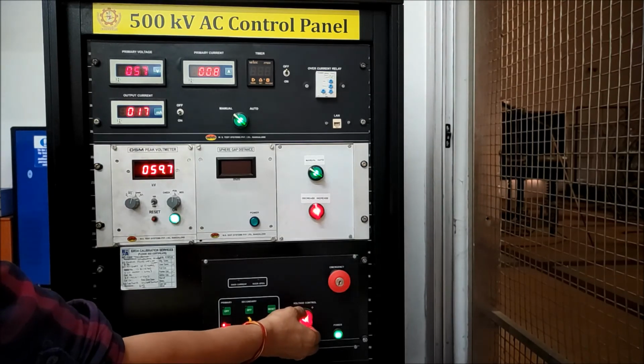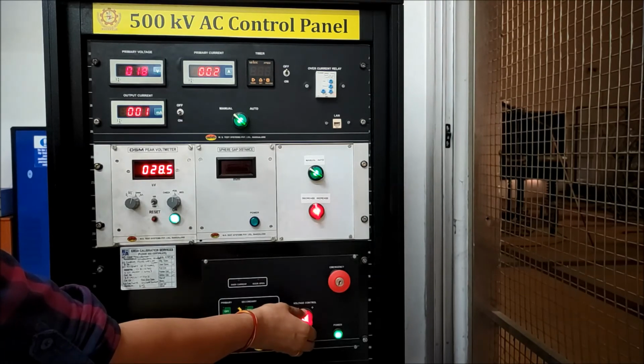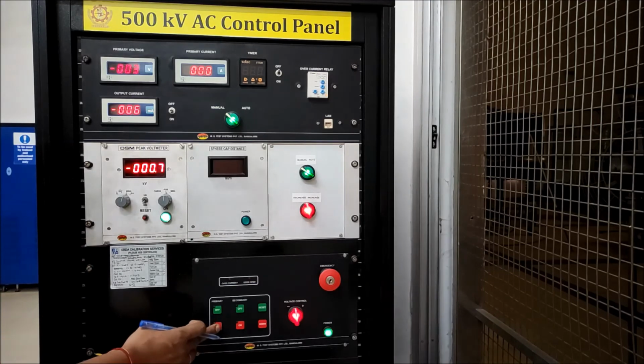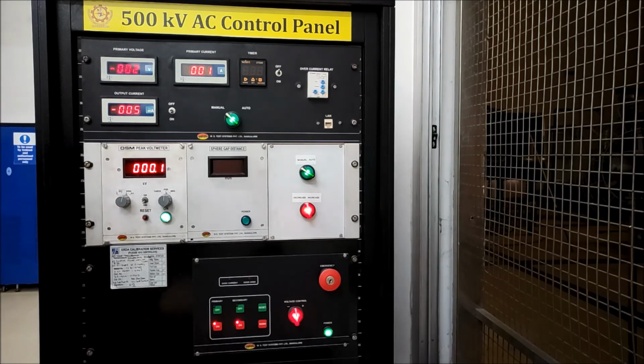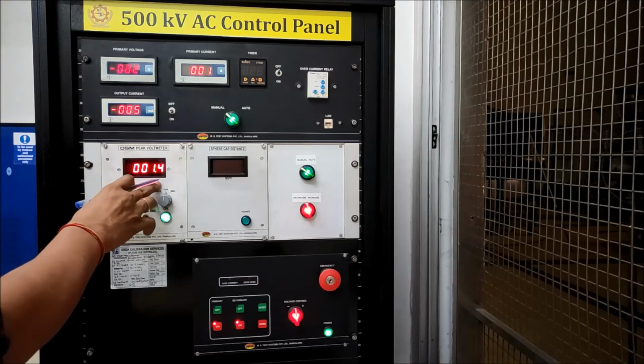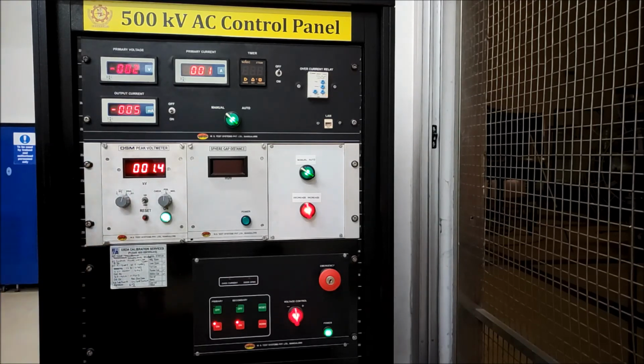Then the sphere gap distance is increased to 1.2 cm. Then again start your experiment. Now change the sphere gap distance to 1.2 cm, then start our experiment. Follow the same process: first switch on the primary, then the secondary, then increase the voltage. At how much voltage flashover occurs, take that voltage. This is the voltage across the whole string, not the sphere gap voltage. The sphere gap voltage I have calculated.